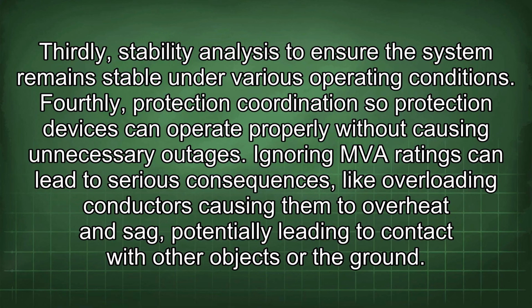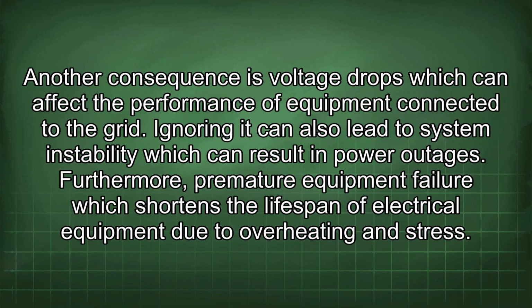Ignoring MVA ratings can lead to serious consequences, like overloading conductors causing them to overheat and sag, potentially leading to contact with other objects or the ground. Another consequence is voltage drops, which can affect the performance of equipment connected to the grid. Ignoring it can also lead to system instability, which can result in power outages. Furthermore, premature equipment failure, which shortens the lifespan of electrical equipment due to overheating and stress.